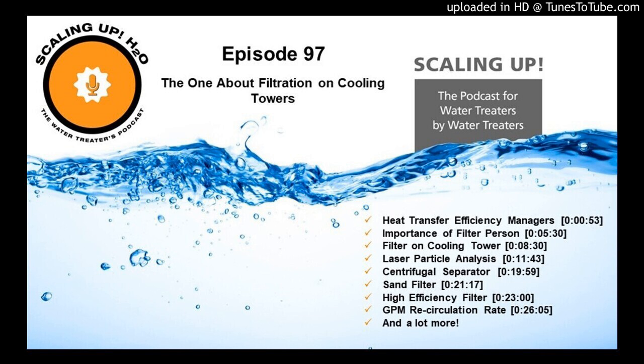So blowing water around in the bottom of the sump to keep the sump clear makes it look better to the customer. But you're not removing the particulate, you're sending it into the system. And the idea that if you've got suction in the sump and that you're actually going to be sucking the particulate out, it's just not rational, not technically accurate. It's not. When you create turbulence in the sump, the large, 1,000-gallon a minute flow rate out of the bottom of that sump is taking all that particulate out of there. Your 100-gallon a minute filter is not removing particulate. That particulate is going where the flow rate is. So it's all going in the system.